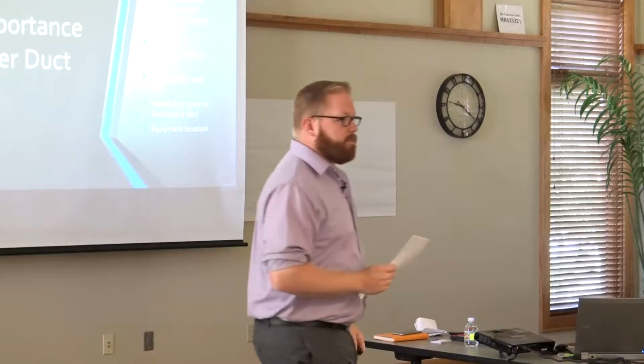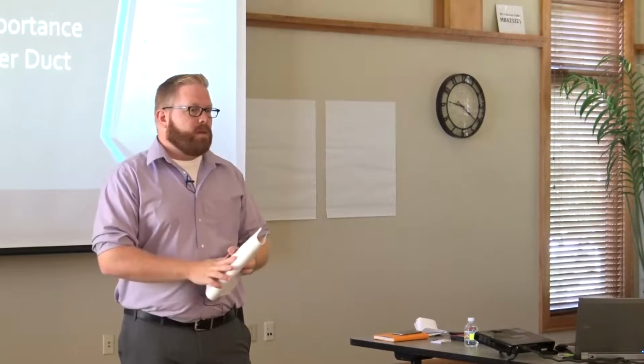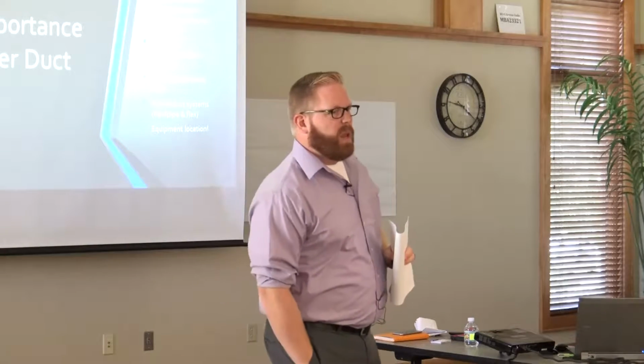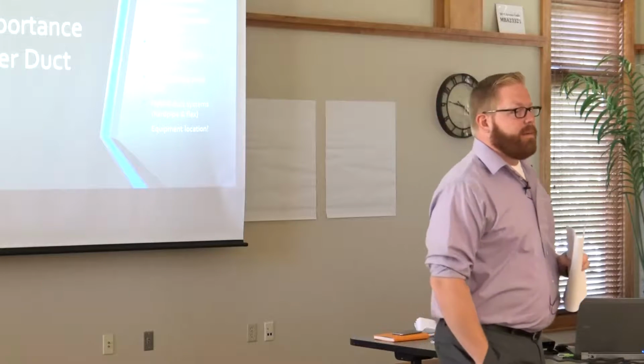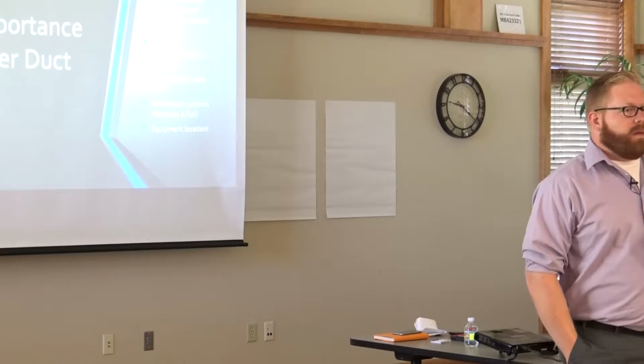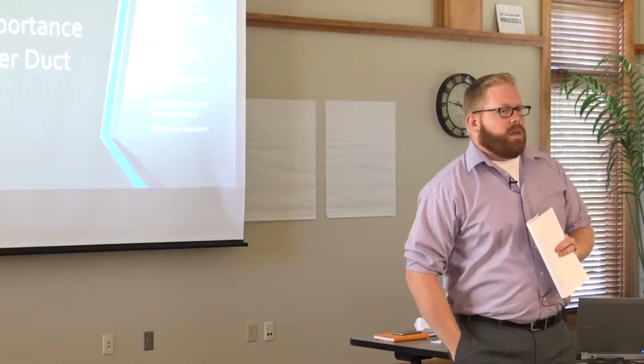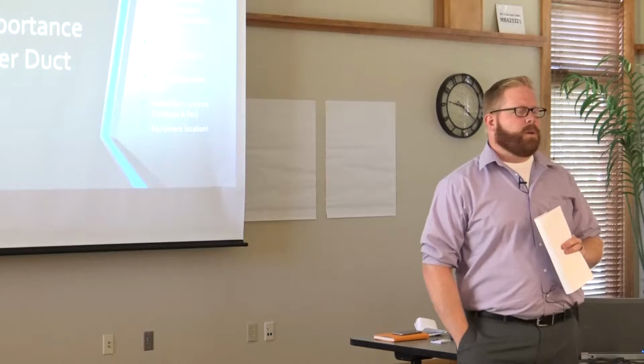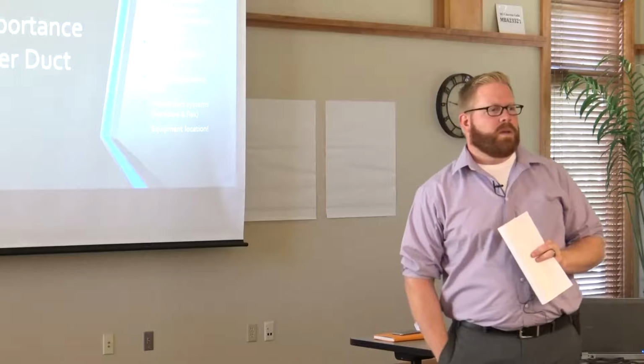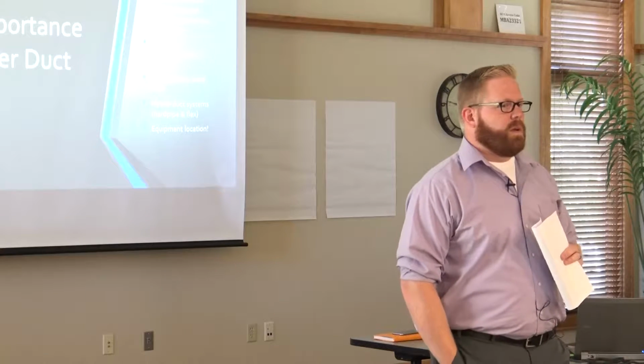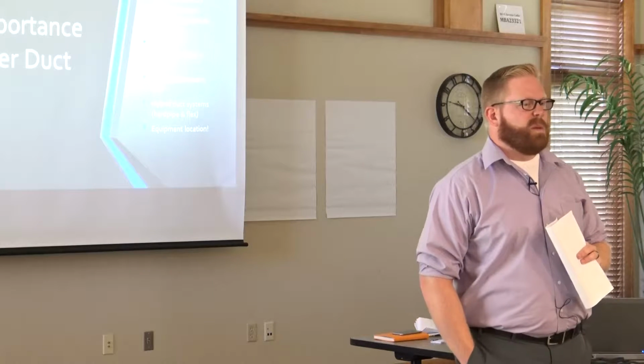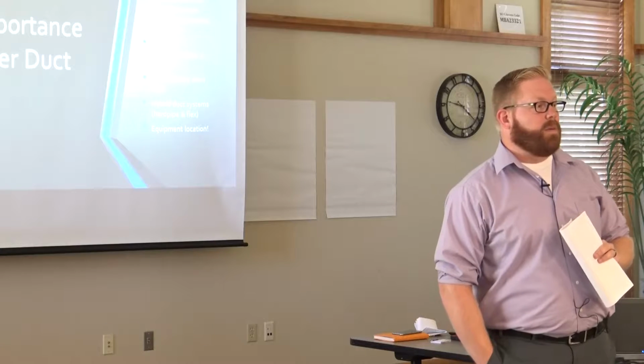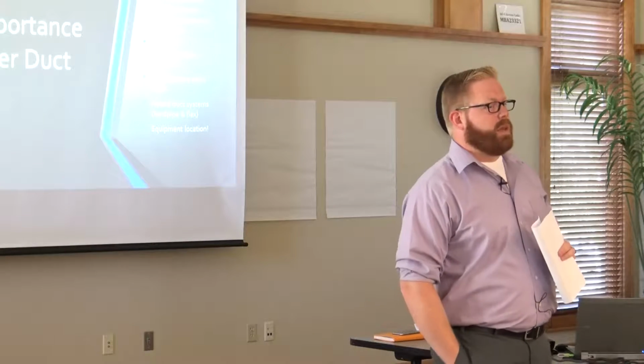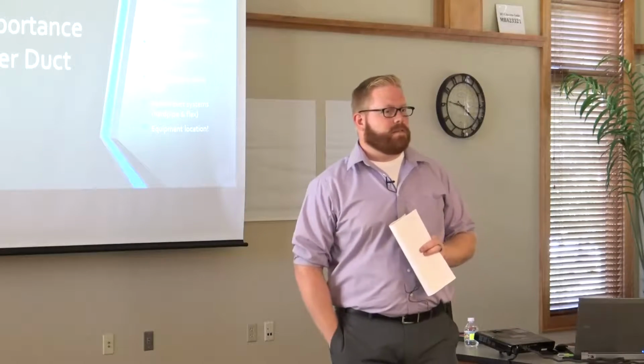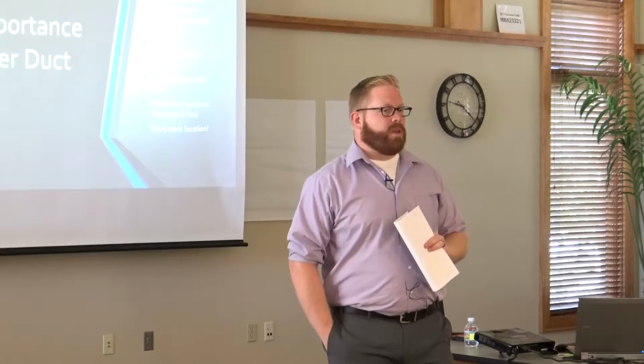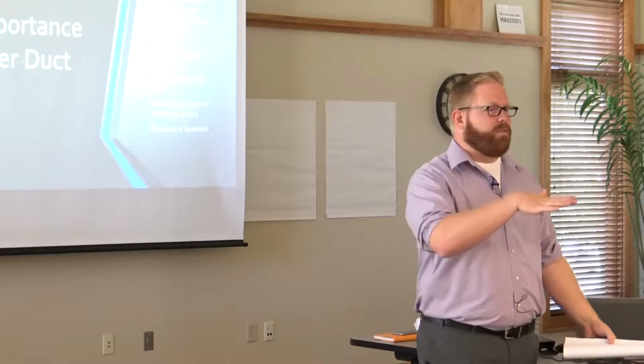The common sin for residential is the 4-inch flex for the bathroom exhaust fan, right? Correct. And what I've been speccing is 6-inch insulated flex, and you keep it not more than 10 feet long before it connects to a rigid duct. Right. Yeah, the maximum length that it's supposed to be is up to 14 feet of flex. So if you're over that 14 feet, again, the boxes come in a 25-foot section.